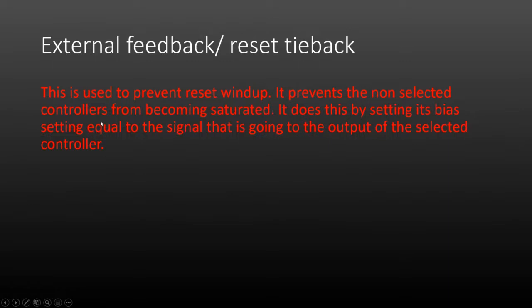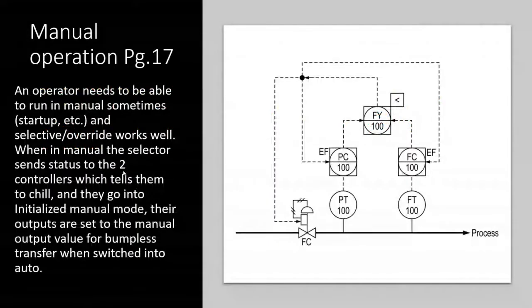It prevents the non-selected controller's output from becoming saturated by setting its bias equal to the signal going to the output of the selected controller. So even though it's not technically doing any work, it is responding to the same signals as the device that is doing the work. Let's address certain circumstances when you'll have discrepancies — one of those is when you're in manual operation, sometimes during startup.